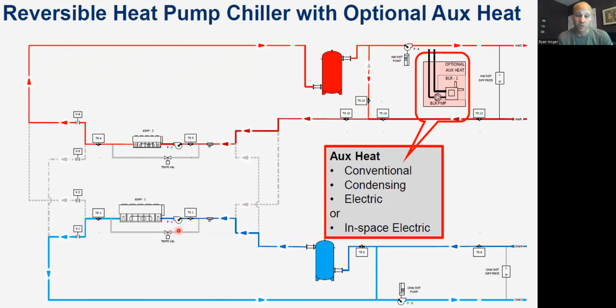So this one is designed for, let's say it's wintertime. This one is designed for the amount of cooling I need in the winter, and the other is designed for the amount of heating that I need in the winter, perimeter zones, things like that. But come summertime, I don't need hardly any heat in this case. Forget about domestic water in this scenario. This is just a heating building, right? I don't need any heating in the building, but I do need more cooling.